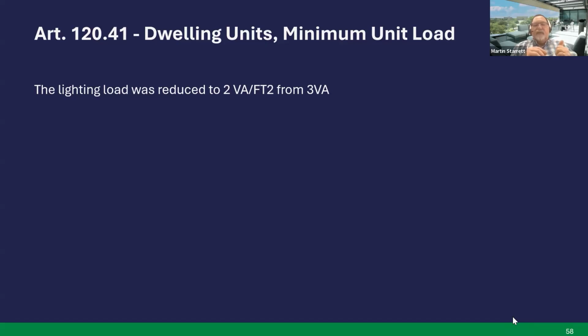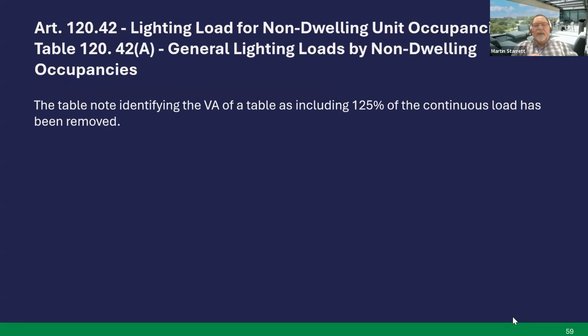So the 120.41 dwelling unit minimum unit load has been reduced to 2 VA per square foot. Whenever we're doing our service and feeder load calculations, where we used to use 3 VA per square foot for dwelling units, we'll now be able to use 2 VA per square foot. The 3 VA will only be for the branch circuit requirements. Next slide, please.